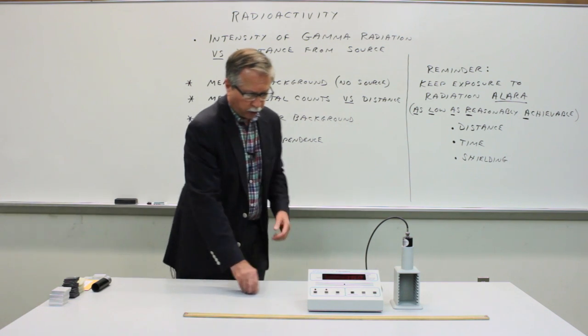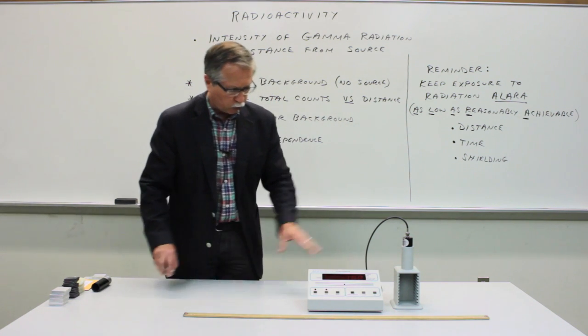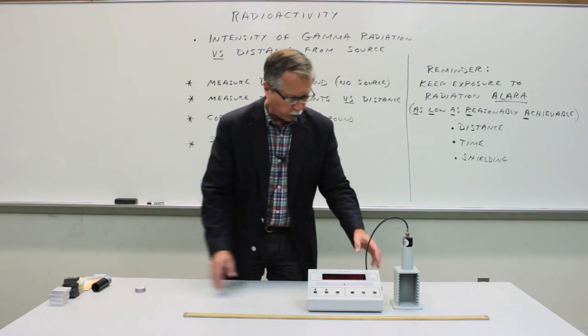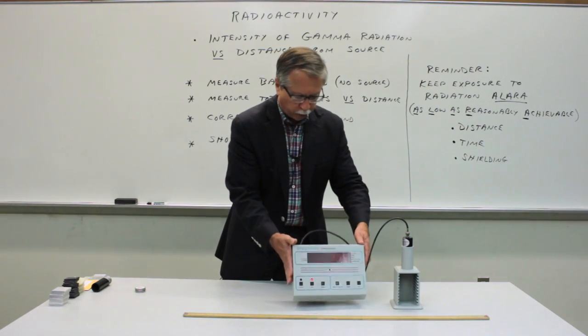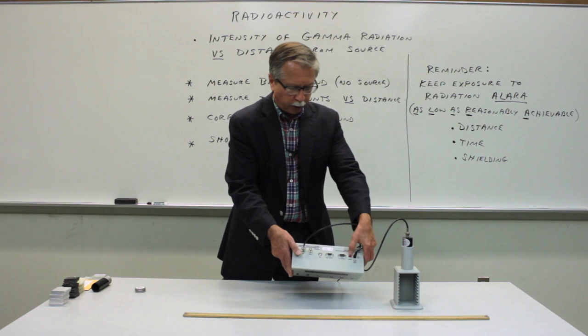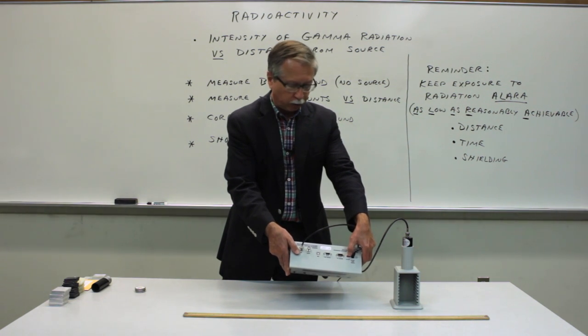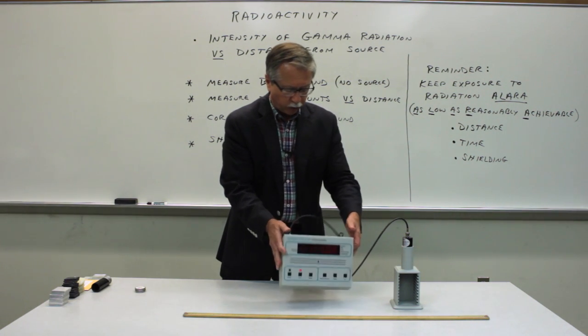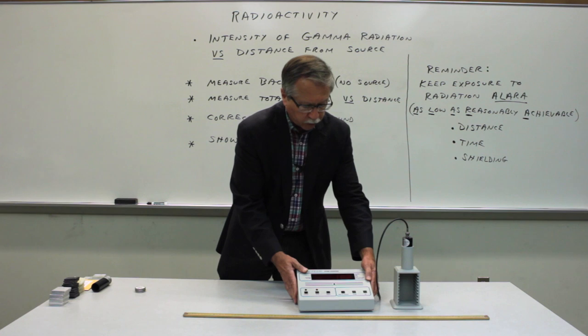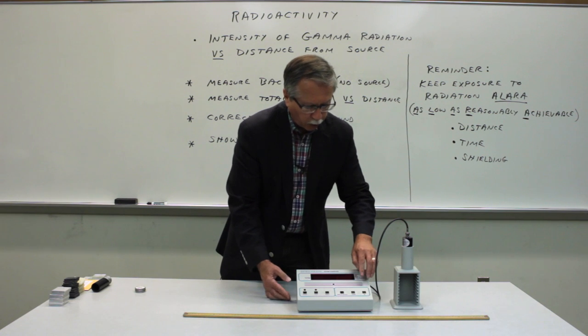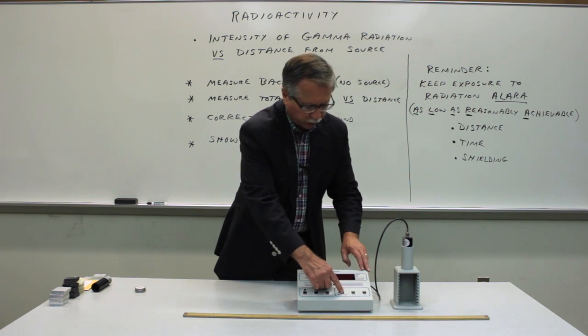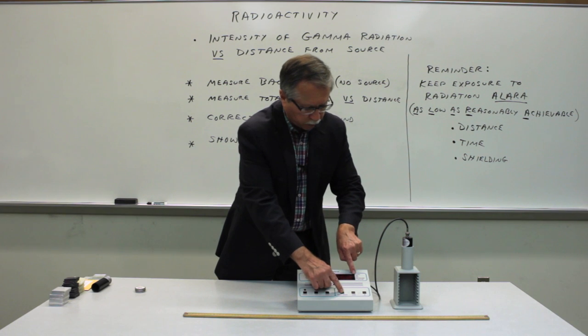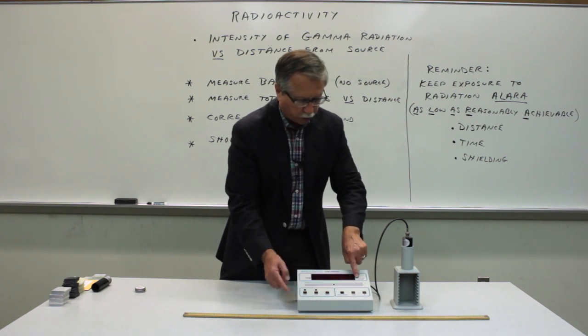What we'll do is first set up the Geiger counter to the appropriate voltage. Just a reminder that the power switch is on the back of the unit — press the red power button and then set the proper operating voltage using the display select function. We'll set this down to high voltage.